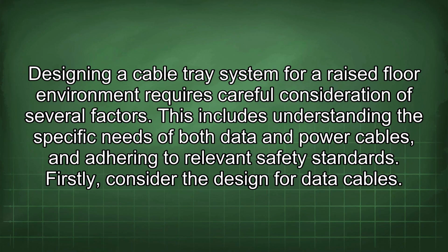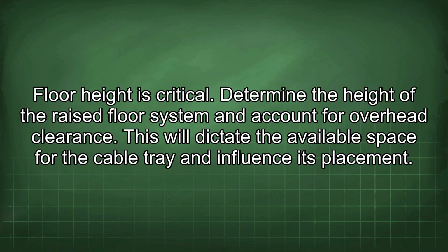Designing a cable tray system for a raised floor environment requires careful consideration of several factors. This includes understanding the specific needs of both data and power cables and adhering to relevant safety standards. Firstly, consider the design for data cables. Floor height is critical. Determine the height of the raised floor system and account for overhead clearance. This will dictate the available space for the cable tray and influence its placement.